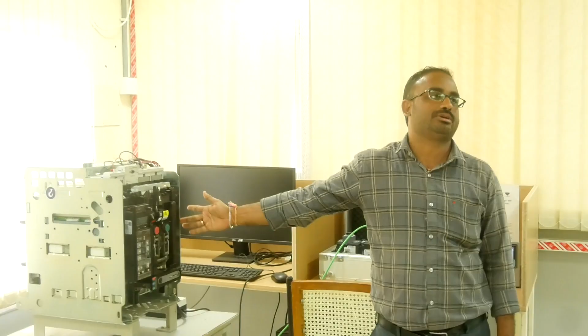Okay, sir, and we also have air circuit breakers, which are used up to a breaking capacity of 55 kiloamperes. The trainees who come for the batches have to learn how to maintain these circuit breakers, how to rack out and rack in, how to use the ETU functions to trip the circuit, how to charge this circuit breaker in the off condition, and how to charge the spring to break the contacts. We also teach about the shunt coil and UV coil, the under voltage coil, and how they operate while a fault occurs.